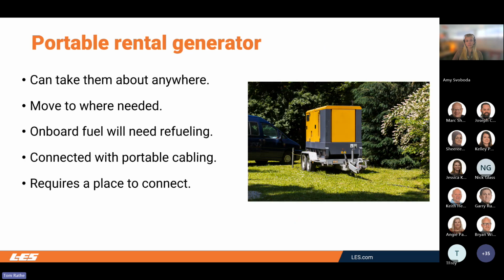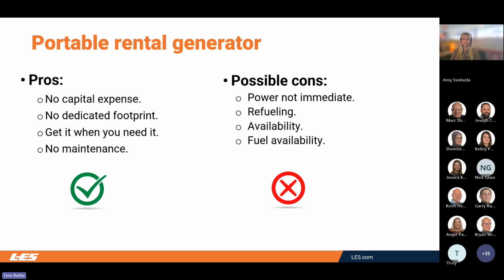So another option to that permanently installed generator would be a portable rental generator. These you would have delivered just as needed. They can have multiple locations set up to connect a portable generator and dispatch it only where it's needed. It would be connected, fueled, and started manually before the critical load is served. It's going to require some periodic refueling, and pretty specific cabling staged ready to go as well—more than just a typical extension cord. It's going to require a place to connect and a means to do that safely: a transfer switch, a breaker, docking stations, and a place to be parked when it's being utilized.